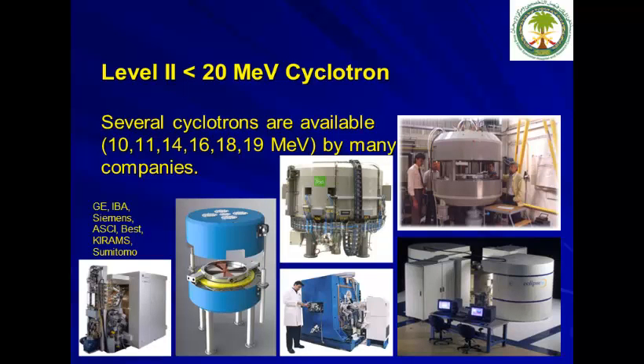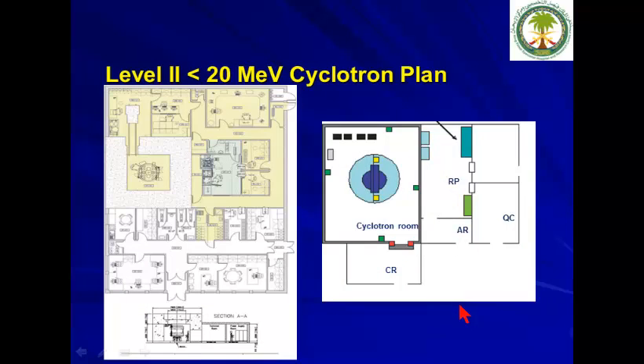The less-than-20 MeV cyclotrons are offered by a variety of companies: GE, IBA, Siemens, ACSI, BEST Cyclotrons, KIRAMS, and Sumitomo. They can be standalone or self-shielded cyclotrons. If self-shielded, you don't need thick walls. If not self-shielded, you will need approximately 2-plus meters of concrete for radiation shielding. The production facility includes radiopharmacy along with quality control infrastructure.